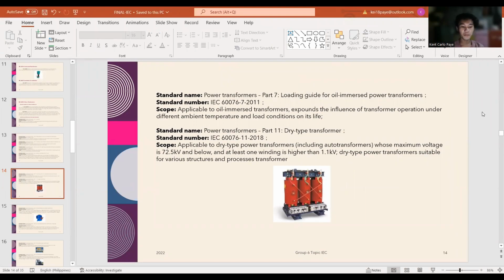So next is the 11th part of the parameter standards that covers the requirements for dry-type transformers, enhancing the capacity to support overloads and resist short circuits. So this standard is applicable to dry-type power transformers, including the auto transformer, whose maximum voltage is 72.5 kilovolts and below, and at least one winding is higher than 1.1 kilovolts. The dry-type power transformer is suitable for various structures and processes.